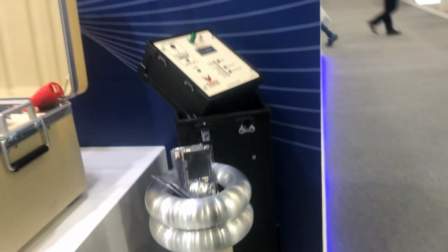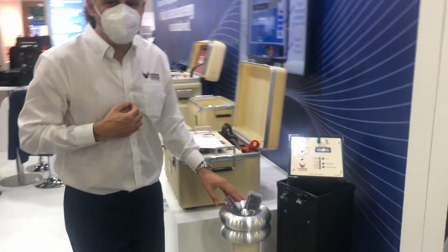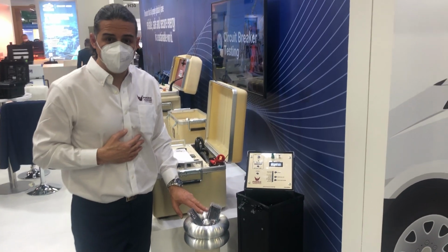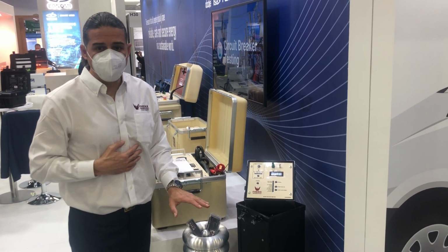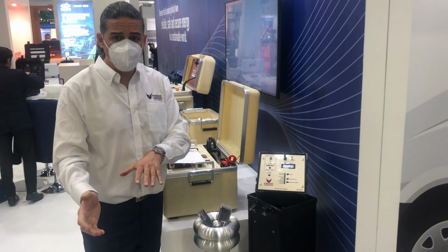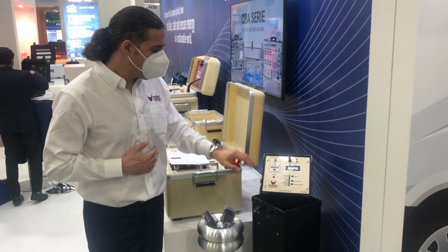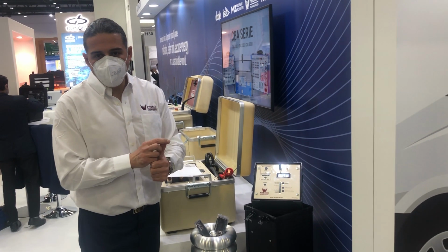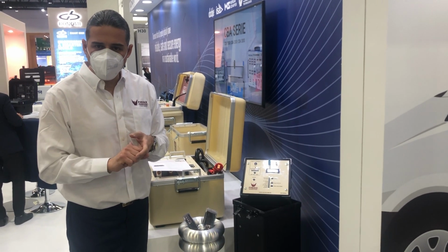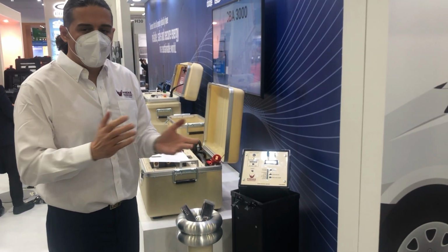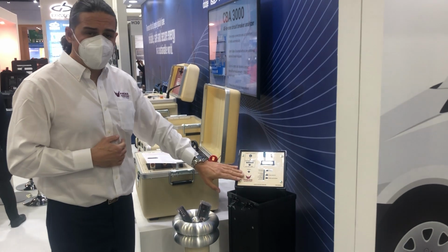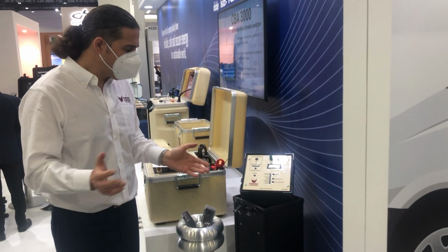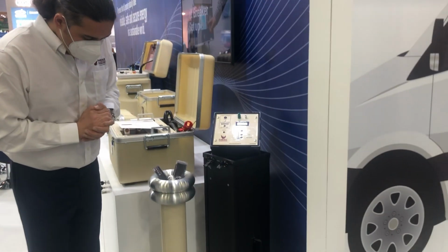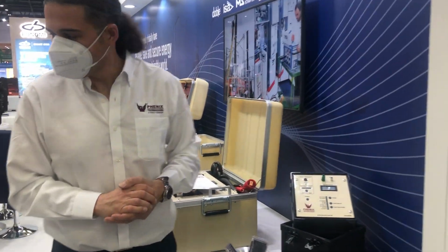And then here, just for a second, we're going to change places, and Martin is going to explain what this thing is. Yes. So this is a universal AC-DC divider that goes up to 200 kilovolts. Highly versatile unit. Whenever you have to measure voltages, be it in the field or in the lab, you can use this divider. It measures peak value divided by the square root of 2, RMS value, average, whatever value you need. It is battery operated, so it is very flexible. You can use it wherever you want. And it's just a fantastic unit to measure voltages up to 200 kV. Thank you, Martin. Let's move on.